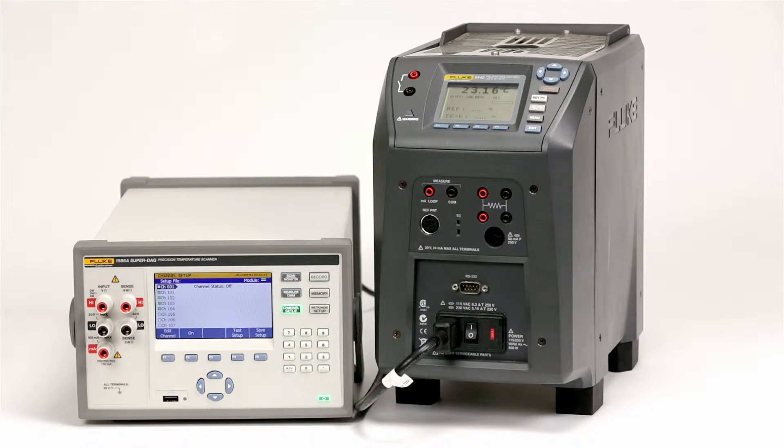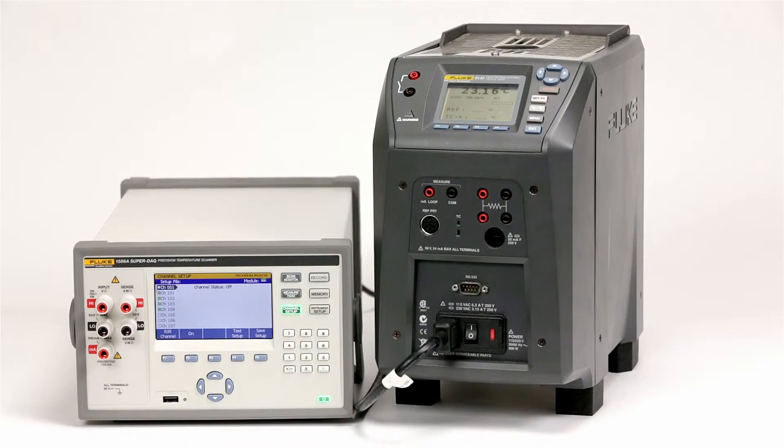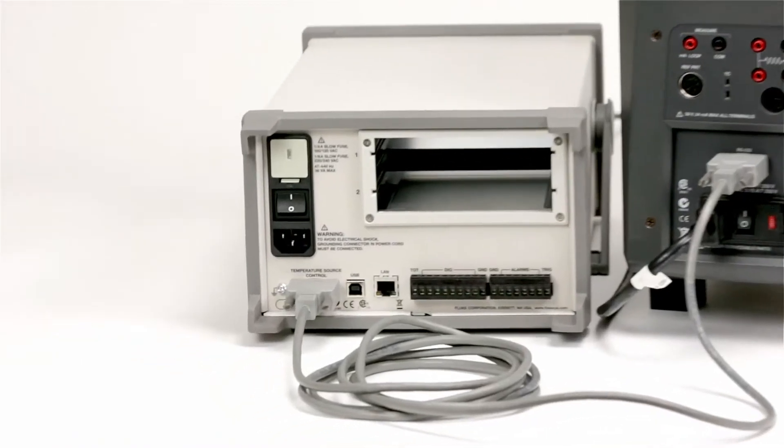The 1586 provides a handy feature for automating the calibration of temperature sensors using a dry well. When connected to a Fluke Calibration Dry Well, the 1586 ramps the dry well through a series of user-defined set point temperatures. At each set point, the 1586 automatically records readings for the reference thermometer and one or more sensors under test.